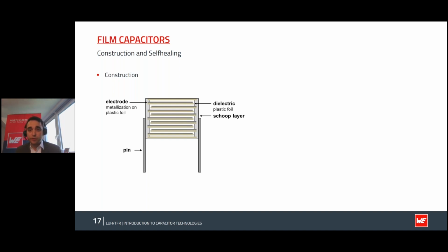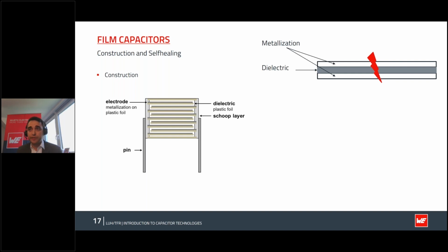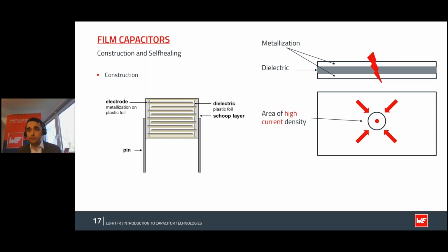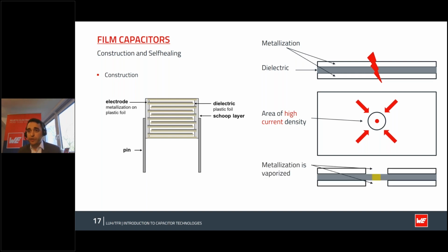This internal structure has self-healing properties. So you'll have the metallization on both sides of the dielectric as it's rolled up. And whenever there's a failure mode, usually penetrating the dielectric, you'll have an area with a short circuit, and it's an area with a high current density. So very much current on a very small area, this generates heat. In fact, it generates so much heat that it will actually vaporize the metallization and even the dielectric in some cases, and then it can generate a plasma to further pull them apart. So the surface area will decrease, but the capacitor will still work as a capacitor at the cost of a small loss of capacitance.